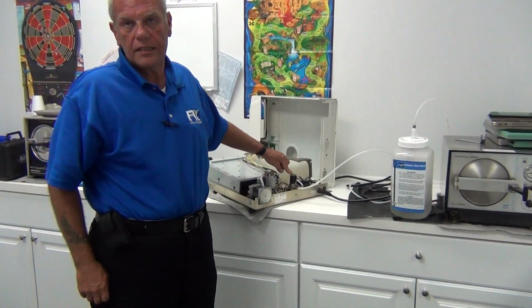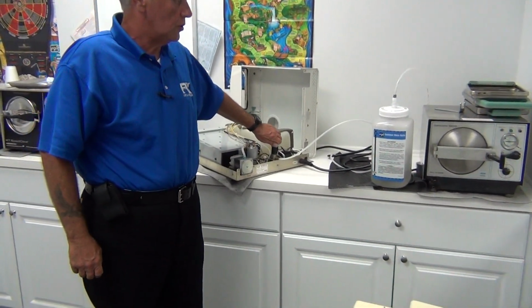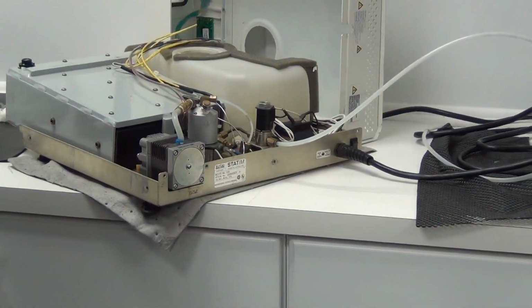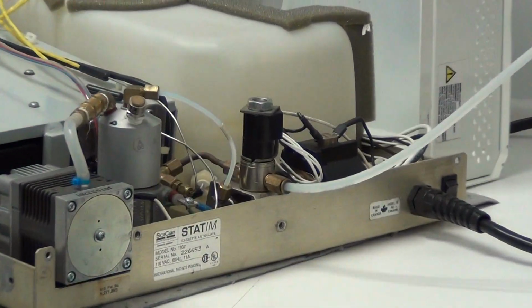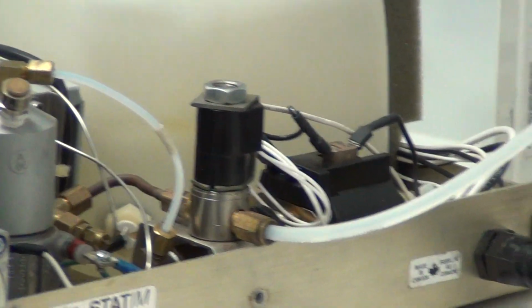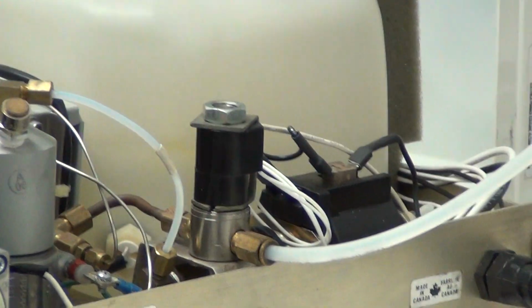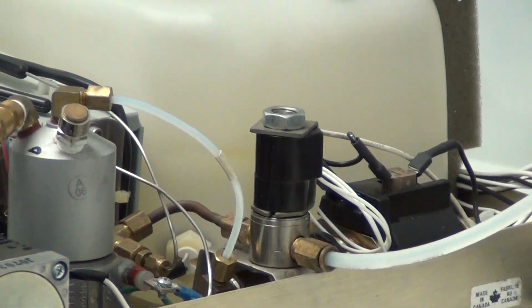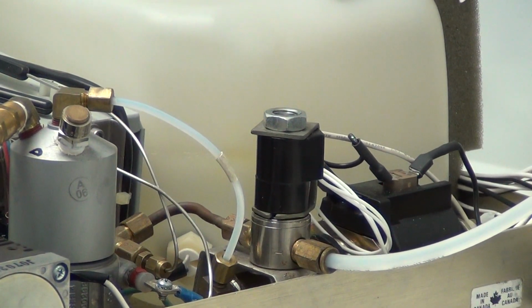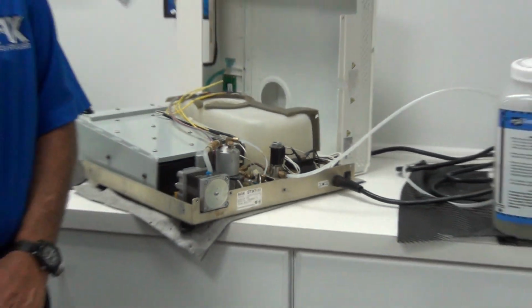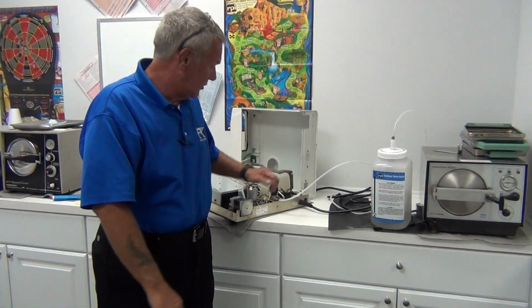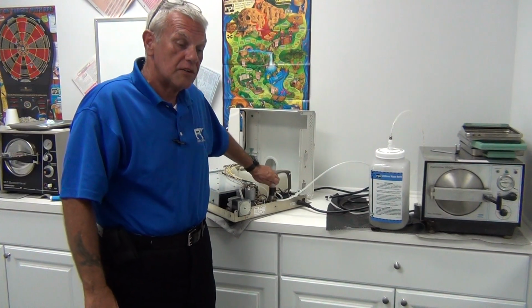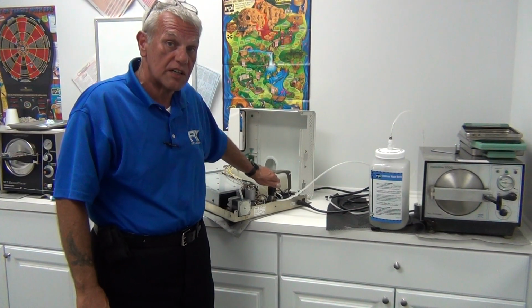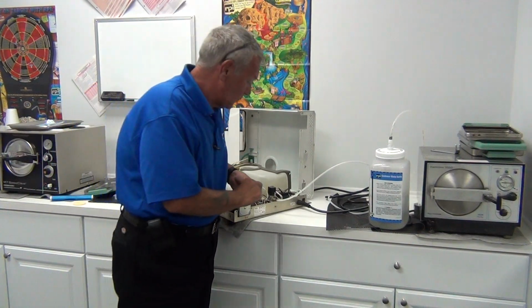We have a solenoid. The solenoid is very, very, very important to the machine working. Sometimes the solenoid will get debris in it and it will not close. DCI and RPI both make a solenoid replacement kit. It's very important to open the solenoid up, not during the cycle, but post-cycle, while the sterilizer is cooling down, and inspect for debris.